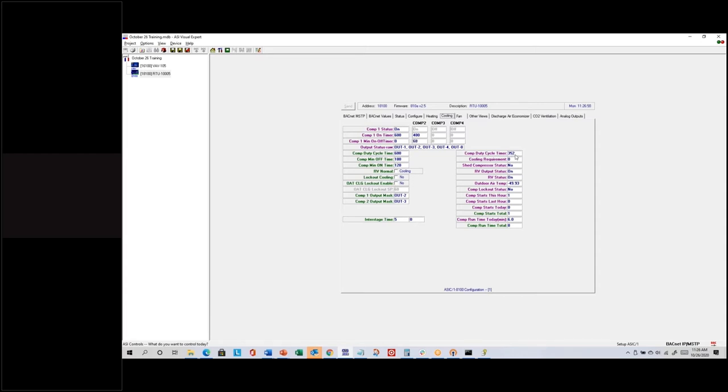Compressor 1 has calculated up to 600 seconds because we're past 50 percent in terms of heating requirements, so compressor 1 just runs indefinitely. Once either the cooling or heating requirements gets past 50 percent, it runs indefinitely. Now at 100 percent, both should be calculating to run full time — and they are.